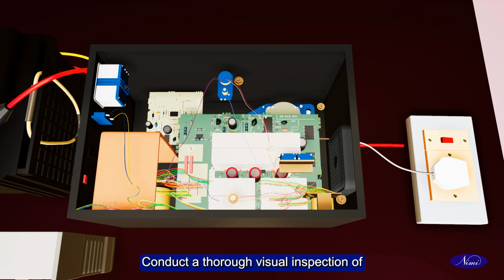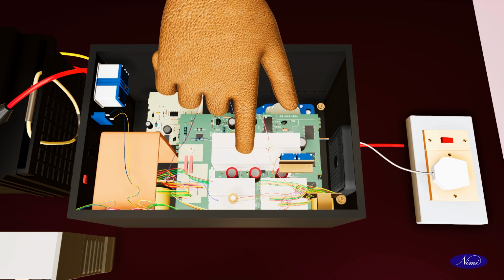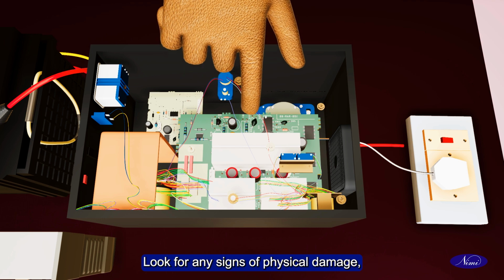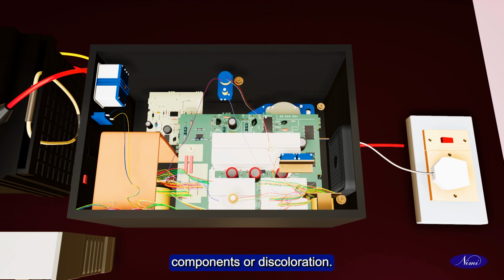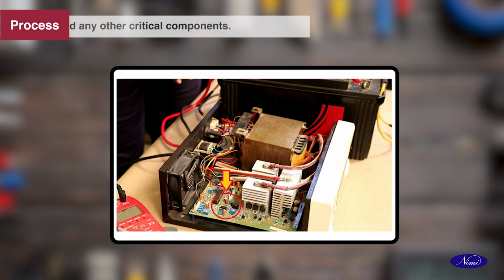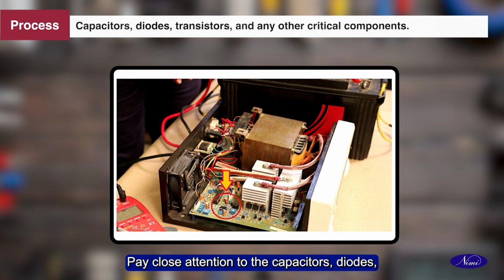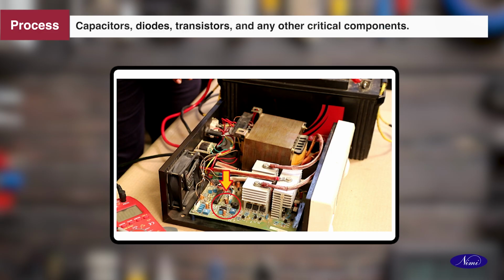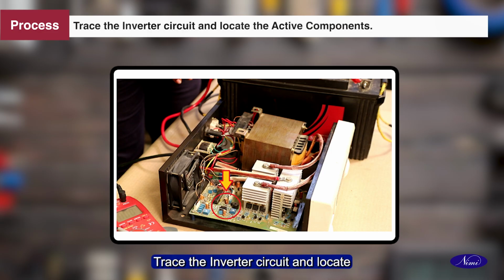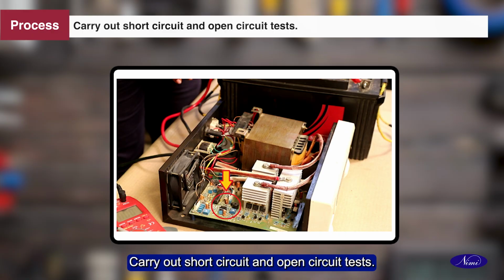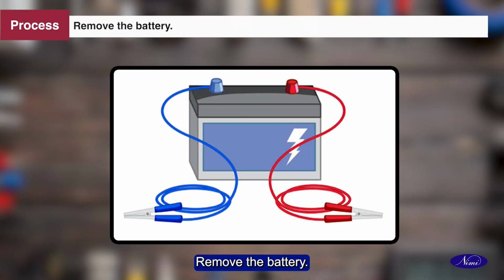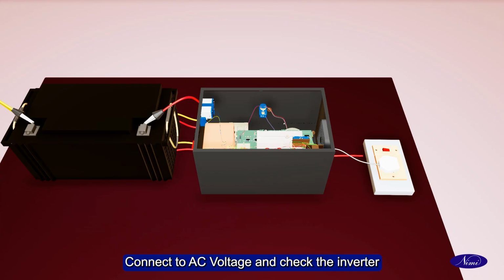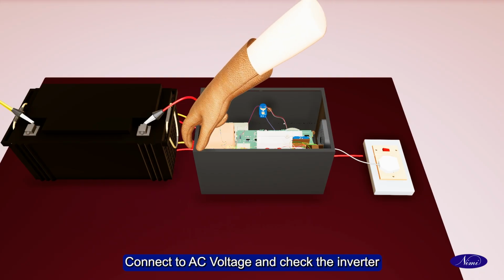Conduct a thorough visual inspection of the inverter circuit and its components. Look for any signs of physical damage, loose connections, burned or melted components or discoloration. Pay close attention to the capacitors, diodes, transistors and any other critical components. Trace the inverter circuit and locate the active components. Carry out short circuit and open circuit tests. Remove the battery. Connect to AC voltage and check the inverter output with the mains on.